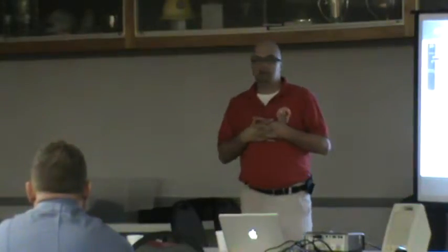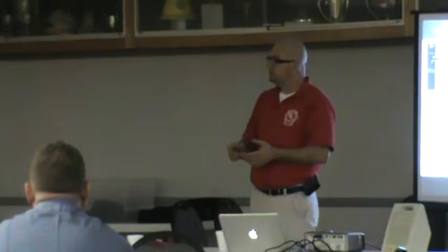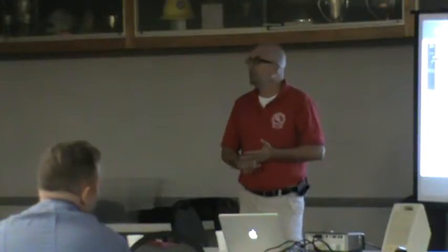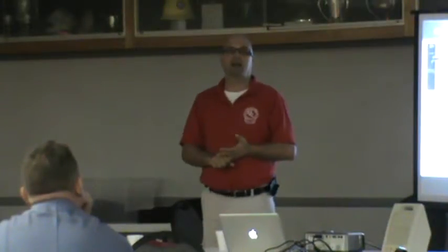Now, we recommend that on all buildings, and this is our recommendation only, in the classes that we teach, if a building goes through a fire escape refurbishment today and gets a sign-off of the confidence test in lieu of a load test, and that building is 50 to 75 years old or 75 to 100 years old, you order an immediate load test on anything that's 75 to 100 years old. Then a load test will not have to be done on that particular building for another 25 years.